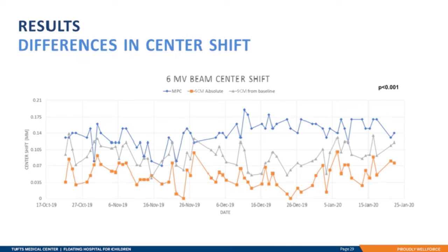Also, since the daily QA3 is used for baselines in SunCHECK machine, if the device isn't perfectly centered for the baselines, then that shift influences all future measurements. Therefore, we looked at the machine performance check data compared to both the reported center shift values from SunCHECK machine, here in orange, as well as the center shift with the baseline shift removed, which you can see in gray.